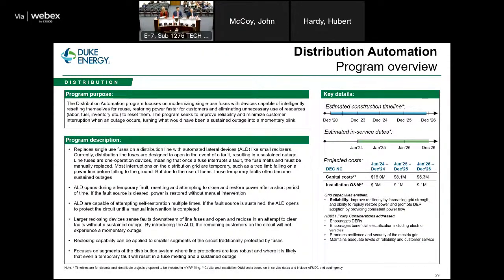Distribution automation modernizes the protective devices on the laterals or tap lines—think of those side streets. This is accomplished by replacing traditional single-use fuses with intelligent electronic devices. Most of our faults on overhead lines are temporary, such as a tree limb falling onto a line before reaching the ground, or a wildlife contact. Traditional fuses are single-operation devices, so many temporary faults become sustained outages, requiring the fuse to be replaced to restore power.